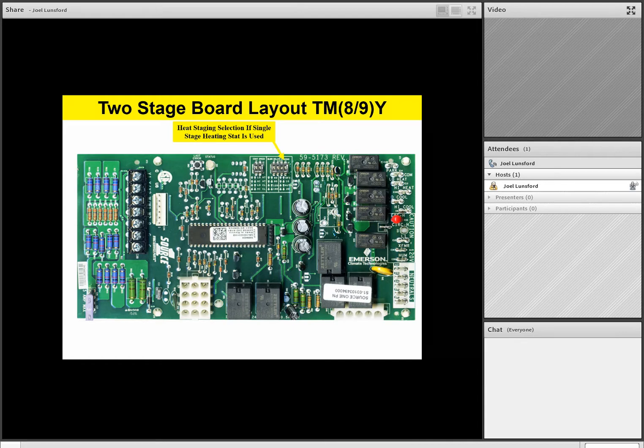Now the third function, and this is some really intelligent function, is called auto, A-U-T-O. So if one dip switch is down, the other dip switch is up. As you take a look at the graphic on the screen, you'll see that for the auto function, the dip switch on the left is down, the dip switch on the right is up. You see the little arrows where it says auto. If it's in the auto position, the board will make intelligent decisions on staging. Now this is, again, if you're stuck with a single stage thermostat.